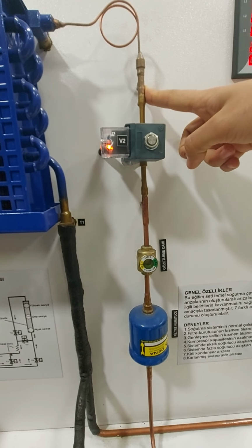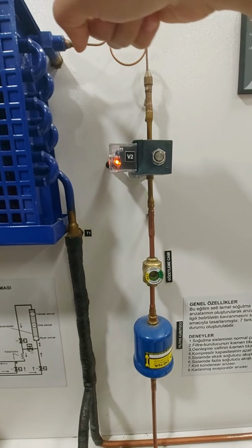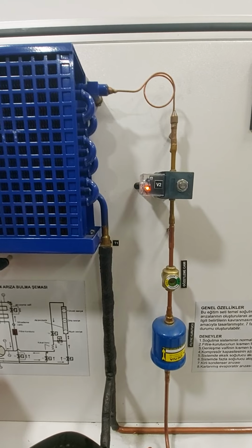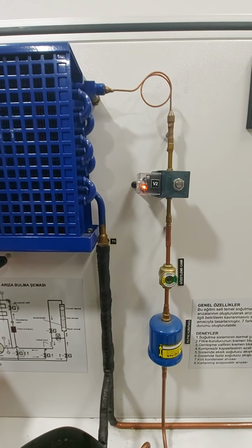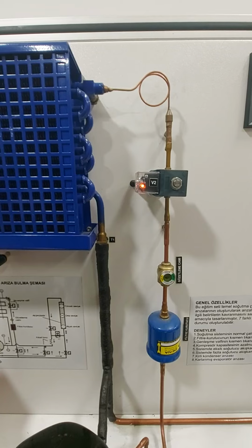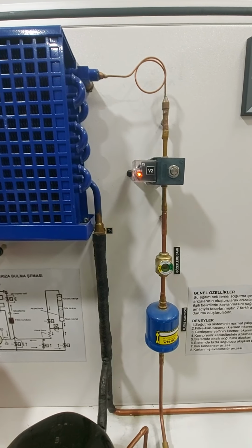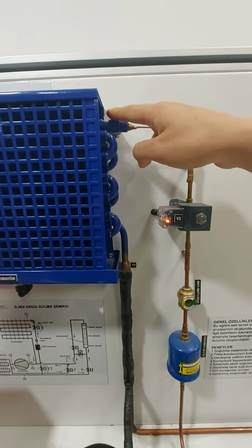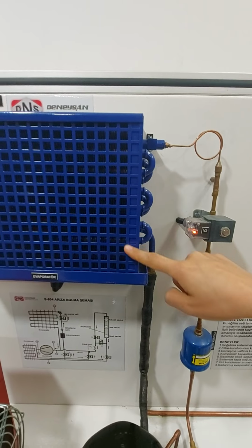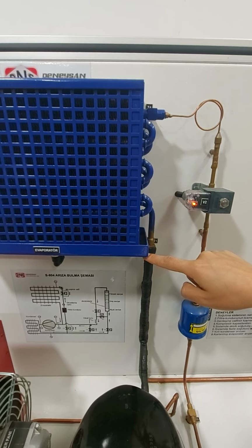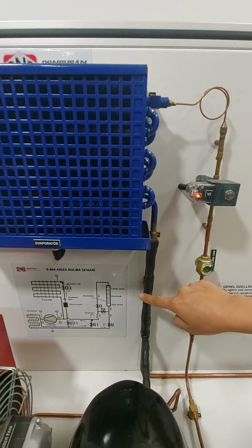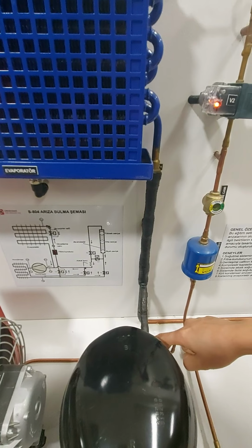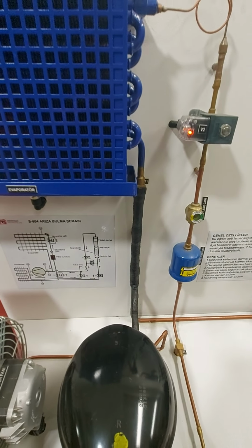The expansion valve meters the correct amount of liquid refrigerant into the evaporator. As the expansion valve meters the refrigerant, the high pressure liquid changes to a low pressure, low temperature saturated liquid. The saturated liquid enters the evaporator and is changed to a low pressure dry vapor. The low pressure dry vapor is then returned to the compressor in the suction line. Thus, this cycle then starts over.